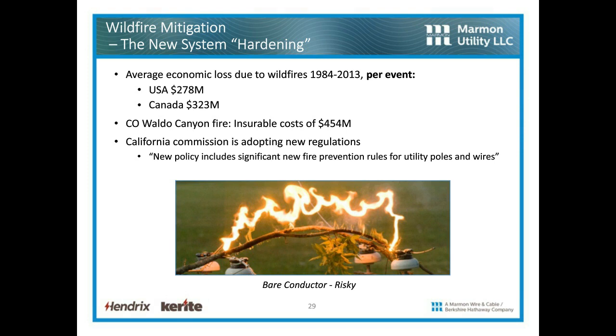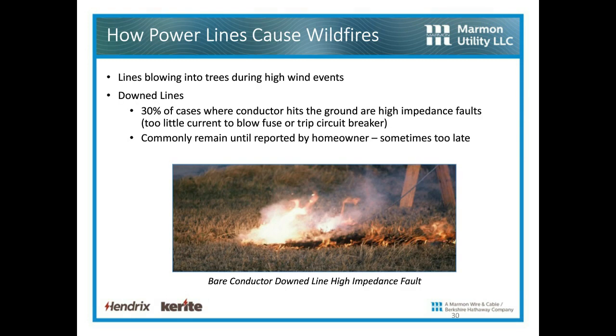There's stuff in the literature saying the California Commission is adopting new regulations, a new policy, including significant new fire rules for utility poles and wires. So how do power lines cause wildfires? Essentially, lines blowing into trees during the high wind events. You think of down lines, 30% of the cases where the conductor hits the ground are what's known as high impedance faults. There's not enough impedance to get enough current to get a fuse or circuit breaker to trip. They commonly remain on that ground until reported by a homeowner. And sometimes, by the time it's reported, it's created a wildfire, and in many cases that's too late.